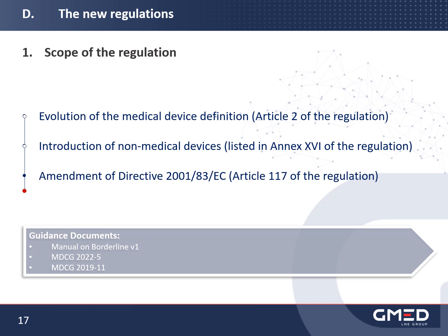The regulation also amends Directive 2001/83/EC through Article 117 of the regulation, which extends the scope of Regulation EU 2017/745 to devices that meet the following criteria. The device and the drug form one integral product. The single integral product is exclusively intended for use in the given combination. The single integral product is not reusable.